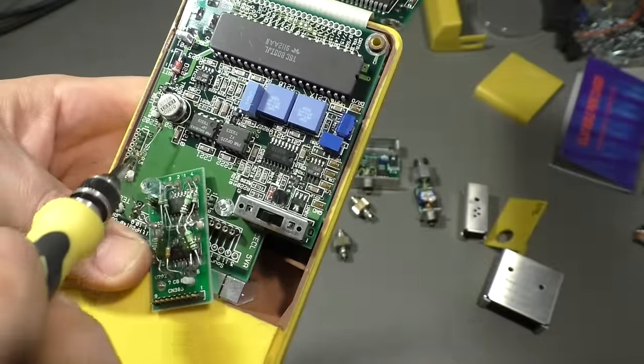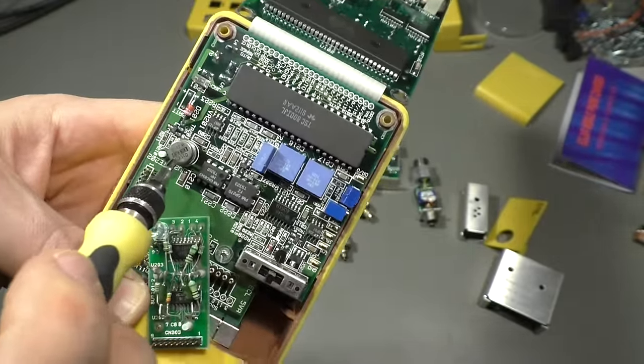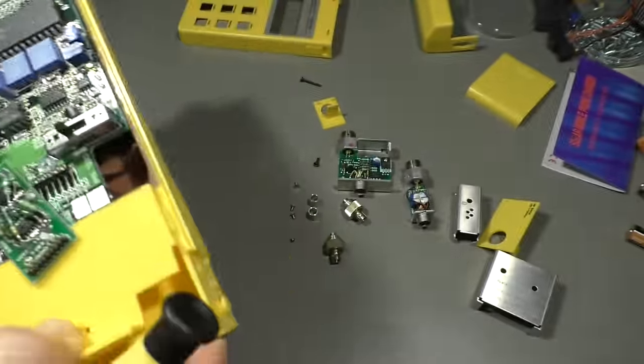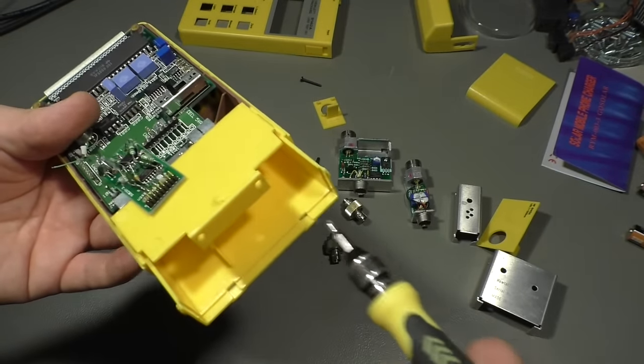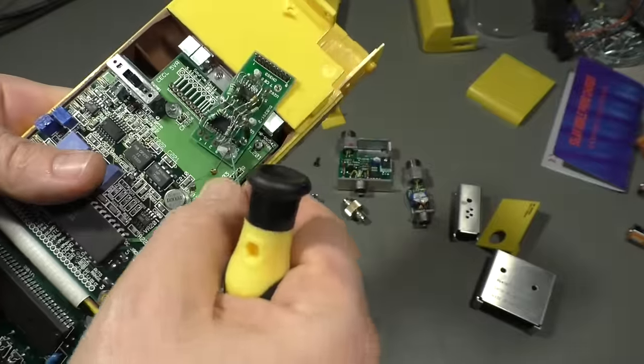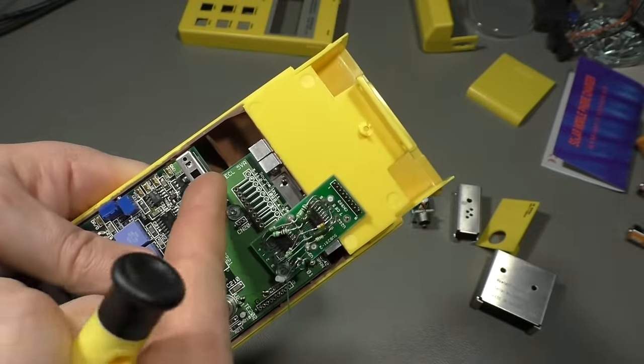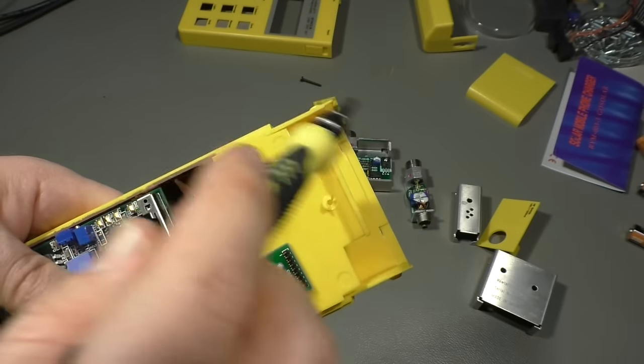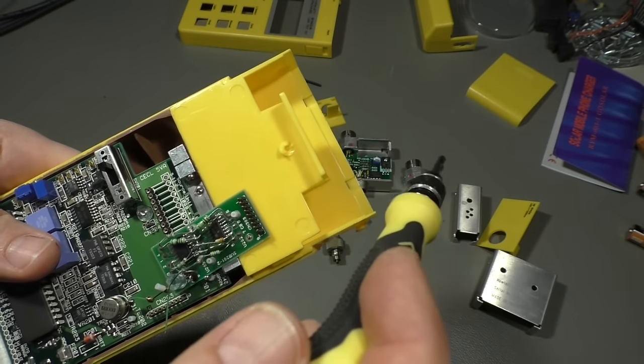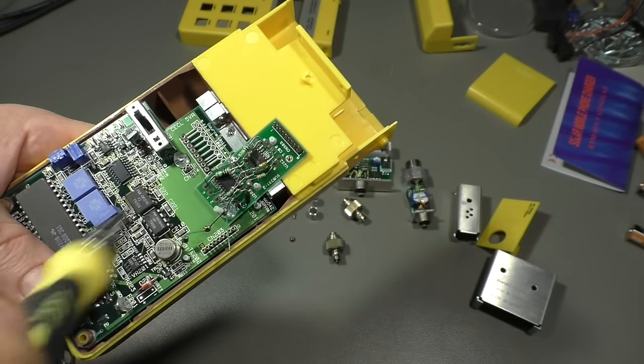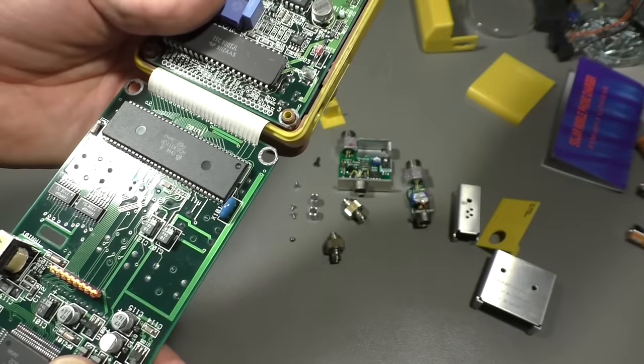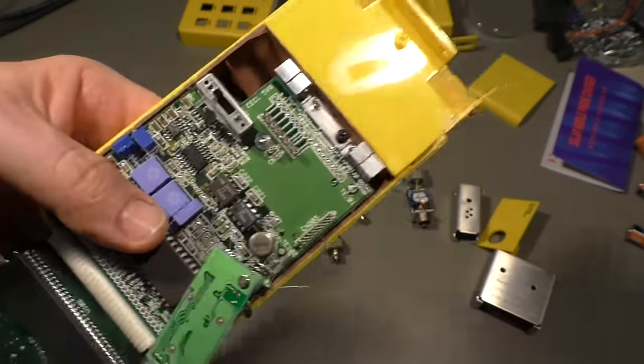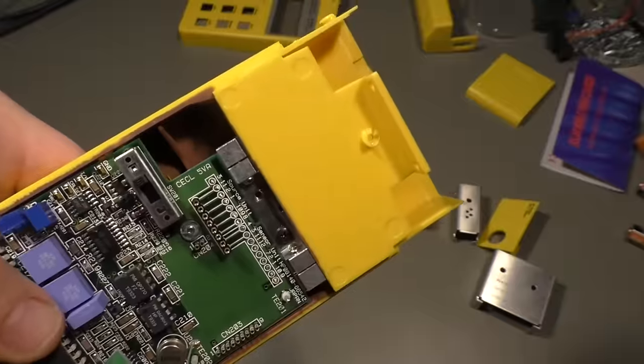And the common goes to that one, the operational amplifier. That's a switch, it has two modes. One mode is measuring what comes to the input, so you can measure the absolute power of the light that comes in. Or you switch it over to loss, then you measure, then you have the source activated, go to a loop of fiber cable, come back and you can measure how much light is lost.